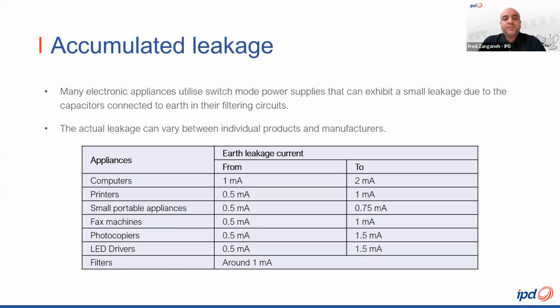Yeah, many electronic appliances utilize switch mode power supplies that can exhibit a small leakage due to the capacitors connected to earth in their filtering circuits. The actual leakage can vary between individual products and manufacturers, so it's worth having a look at the tables provided by manufacturers. This table that we have here can provide guidance on the type of leakage that can be seen on various types of equipment.